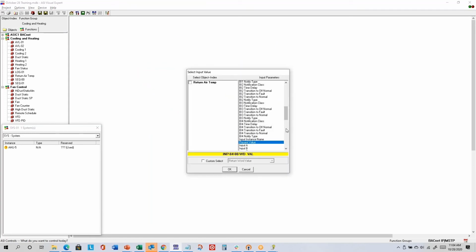then it gives me the list. If I scroll down just a little bit, then between high limit fault and input OR status is the fault status. And that's when we saw it turns on if there's a low limit fault, meaning the wire has been cut or there's no sensor connected, or if there's a high limit fault, which means the input is shorted. Did everybody find fault status in the list? Yes. Okay, good.